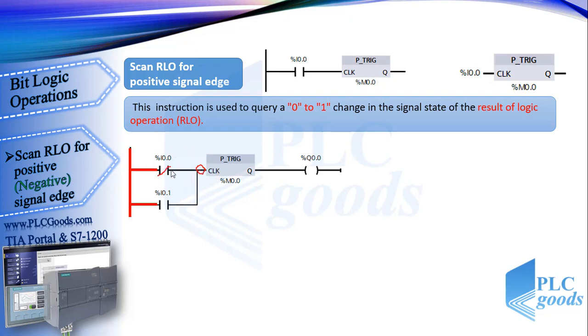When either I 0.0 or I 0.1 is activated, the virtual power — in other words, the result of logic operation RLO — changes from 0 to 1. This instruction detects this change at its input and generates a pulse which makes Q 0.0 turn on for only one program cycle, which is about 5 ms.